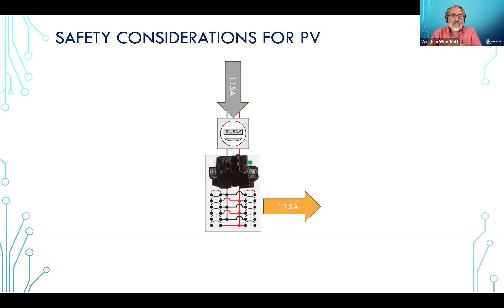Now let's say, for instance, we have that 115 amp load, and we have a rooftop solar system that's pushing 15 amps into the panel. Now the draw that's asked for from the utility is 100 amps. And because that doesn't exceed 100 amps, it's not going to open up the main breaker, which means we're going to be putting 115 amps through a 100 amp panel.